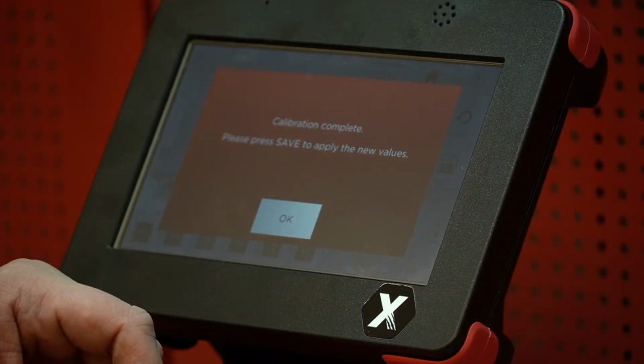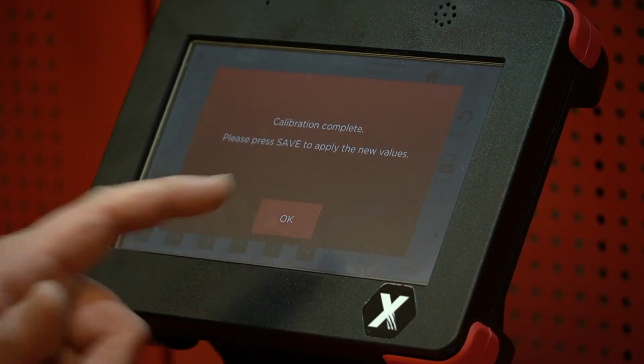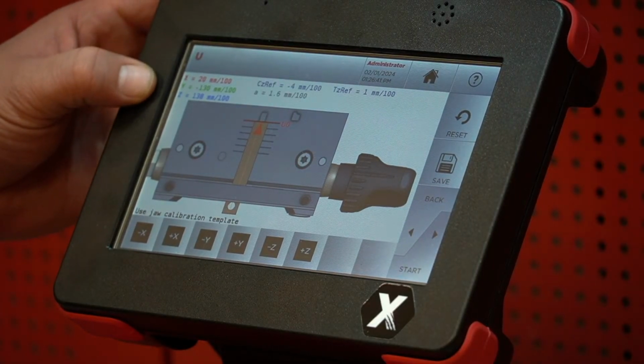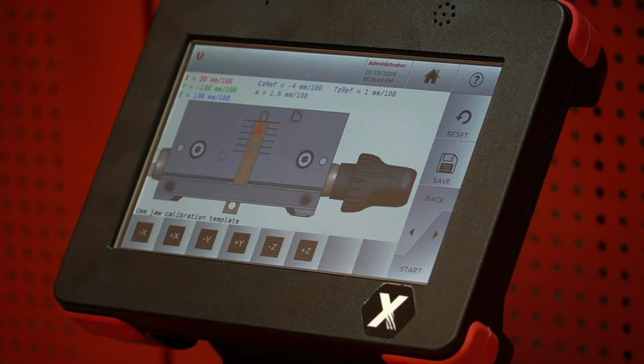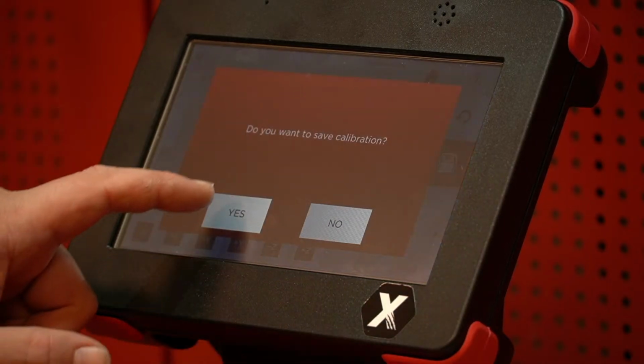Calibration complete. Please press save to apply the new values. Hit OK. And then you look at your X, Y, and Z values. You should have a differential of plus or minus 4. I see that we did have changes here. I remember negative 144 for the Y. It's now negative 130, which is fine. Our X changed also to 20. So we hit save, hit yes, and then we're going to run it one more time.